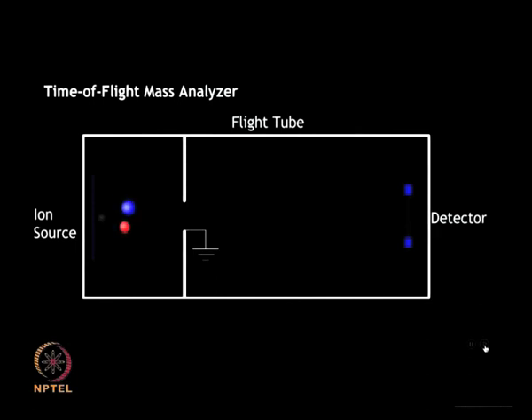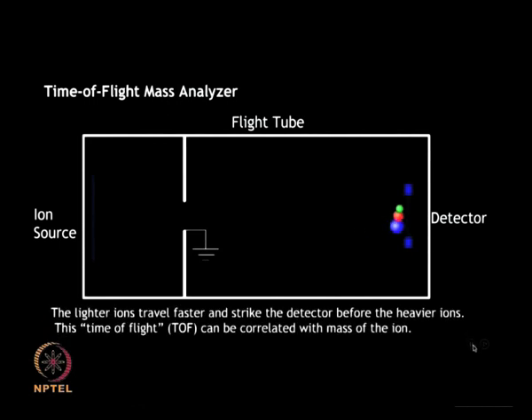The time of flight tube can be operated in linear mode or reflectron mode, depending on the sample to be analyzed. In the case of small molecules, linear mode usually provides sufficient resolution. The generated ions are accelerated towards the detector with lighter ions traveling through the TOF tube faster than heavier ions. The lighter ion strikes the detector before the heavier ion, and this time of flight can be correlated with the mass to charge ratio.